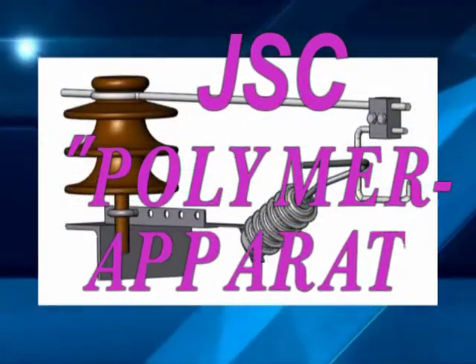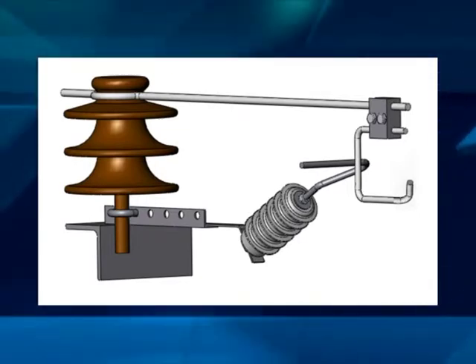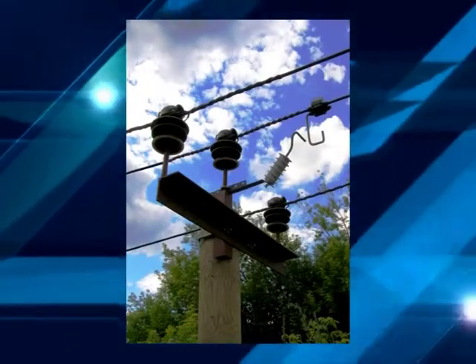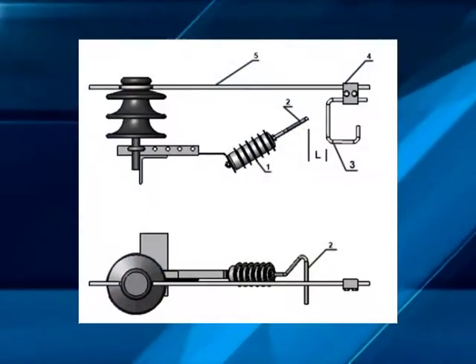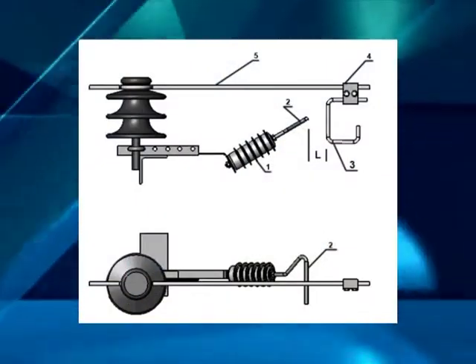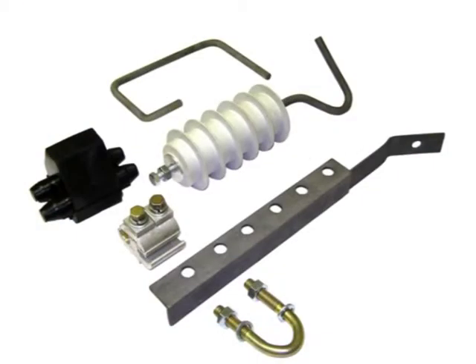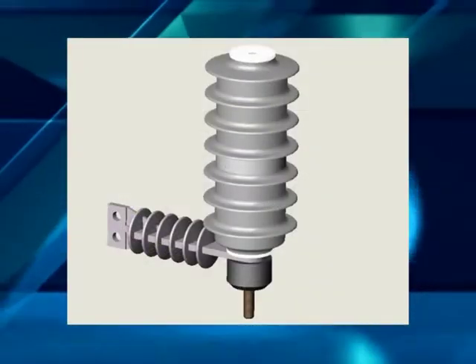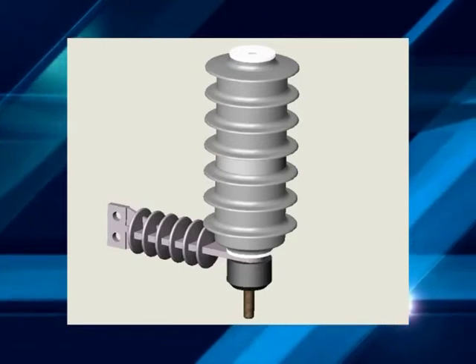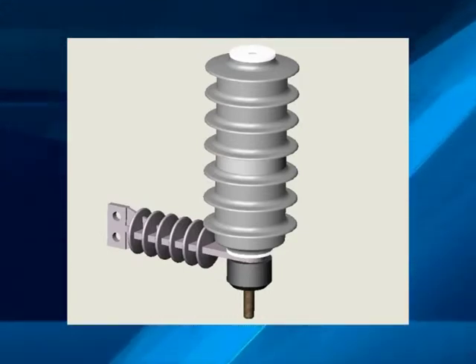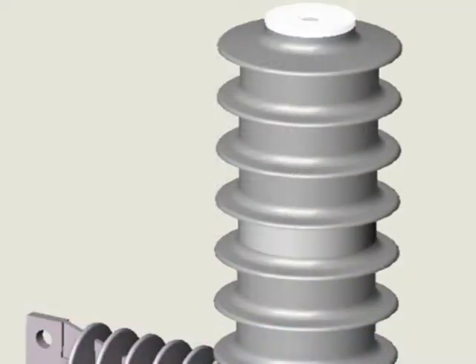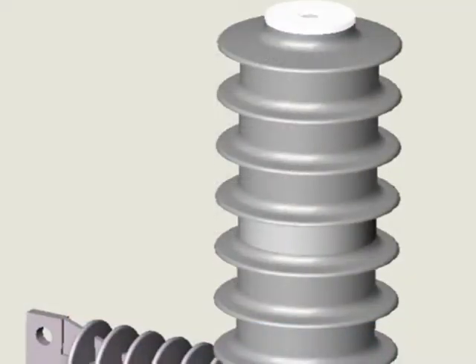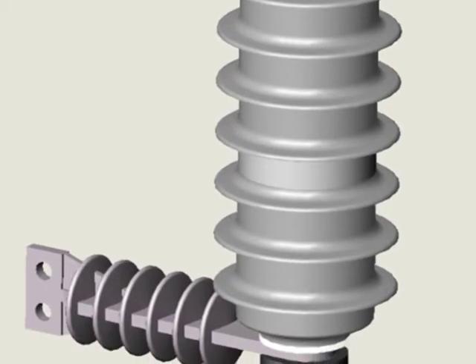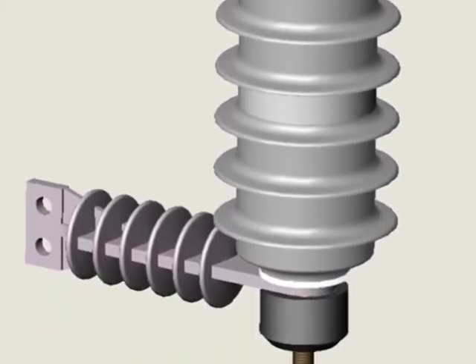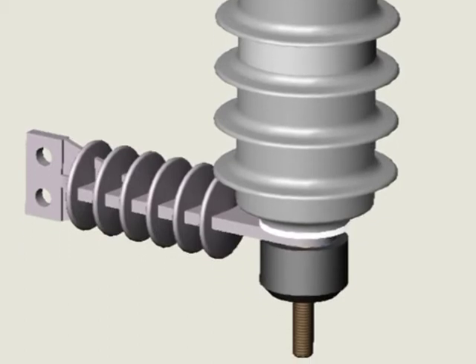The operating principle of the arrestor is implemented also in 6 to 10 kV overhead lines. Since 2006, devices of type UZPN for protecting 6 to 10 kV overhead lines from surges are being successfully used on overhead lines with both isolated and bare wires. Our company produces surge arresters with an insulating bracket and the separator for the voltage class 6 to 10 kV. Such connection of protective devices allows organizing uninterrupted power supply to consumers. In case of unregulated influences, direct lightning strike, etc., and damage to the surge arrestor, the separator breaks the earth circuit and thereby eliminates a steady short circuit.